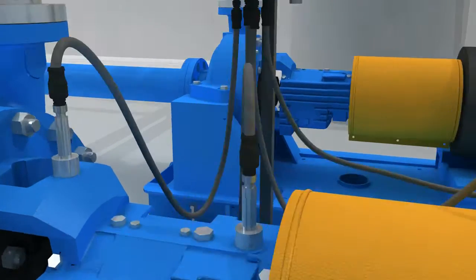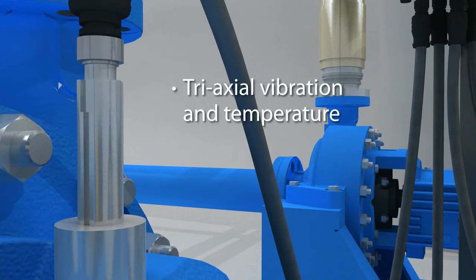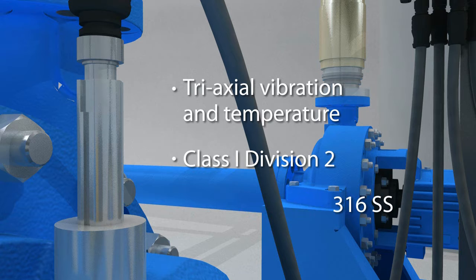ITT offers the industry's only triaxial vibration sensor with temperature data to provide a complete bearing condition. The entire system, including the sensor, is rated for hazardous Class 1 Division 2. The sensor housing is 316 stainless steel, which is environmentally rated for NEMA 4X and ingress protection rating IP67.